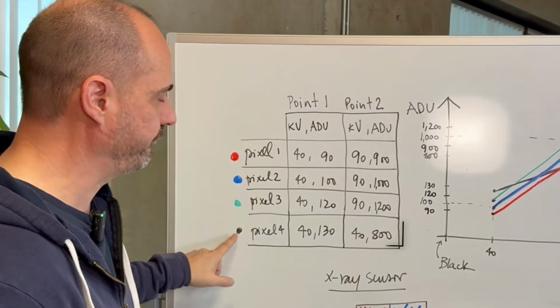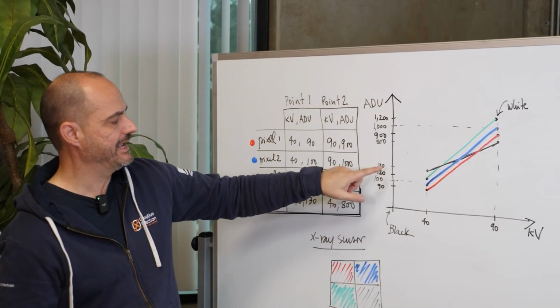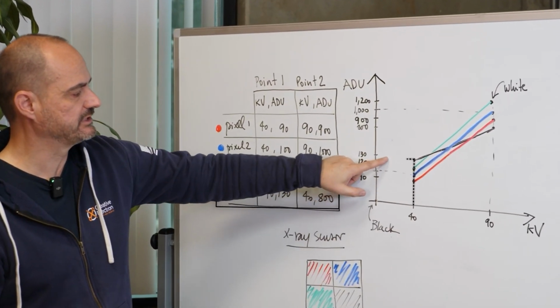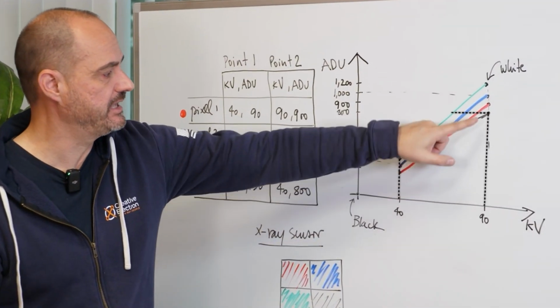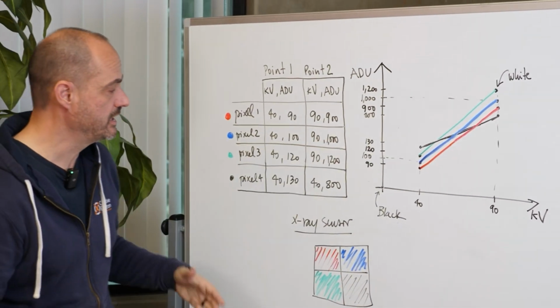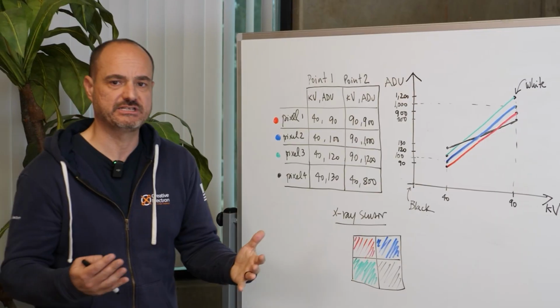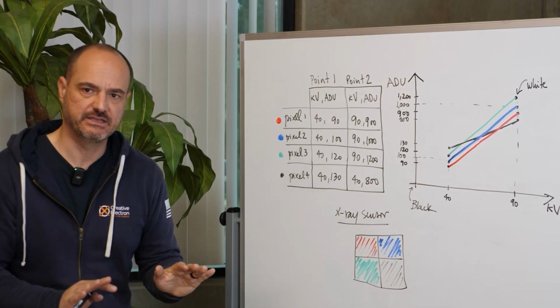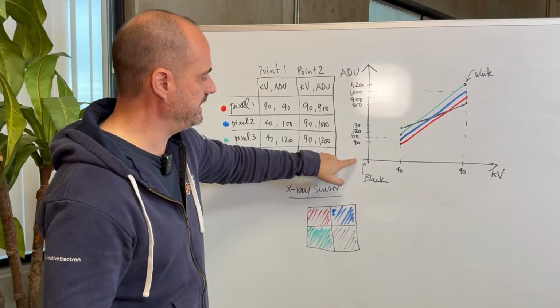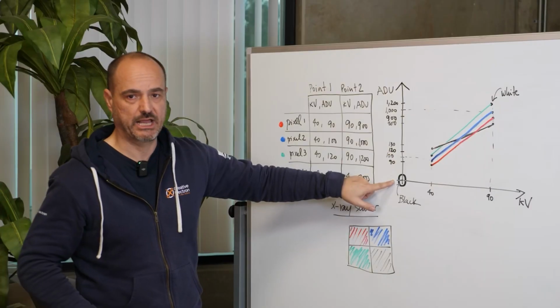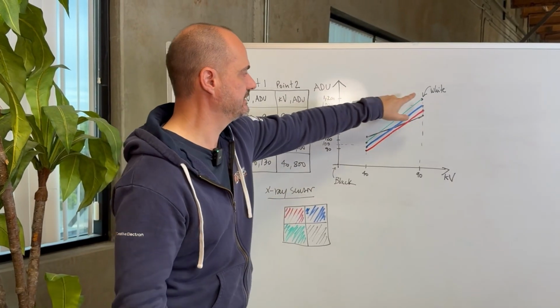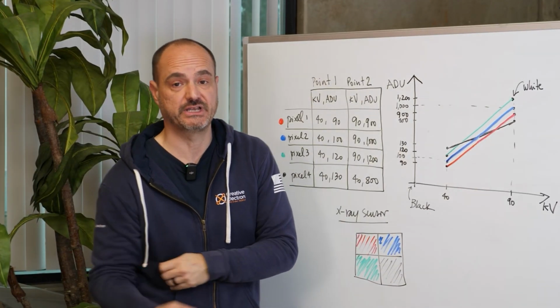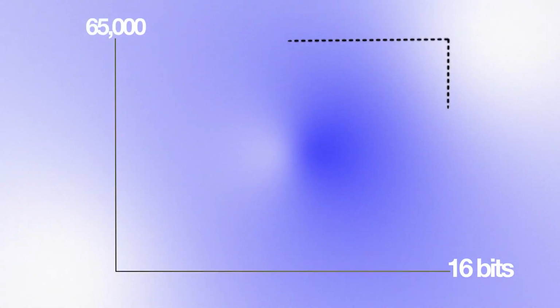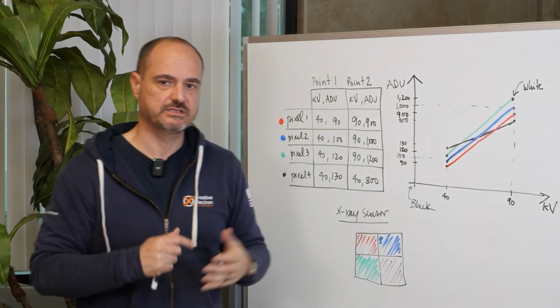And check out, pixel 4 is a little bit different. Pixel 4 at 40 kV gives us 130, but at 90 kV, it gives us 800 ADUs. So each pixel in an X-ray sensor is going to behave slightly different. So what? In this ADU scale, 0 is black. It means there's no radiation, and the top of the ADU is white. For example, most of our sensors are 16 bits, so the top ADU will be 65,000 and some change. That means you have a white image, so it's fully saturated.